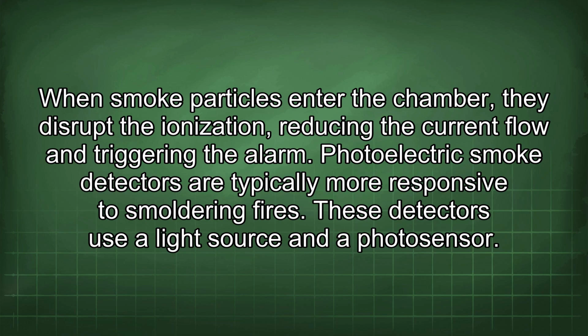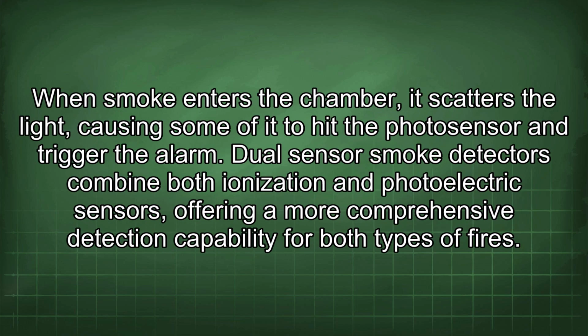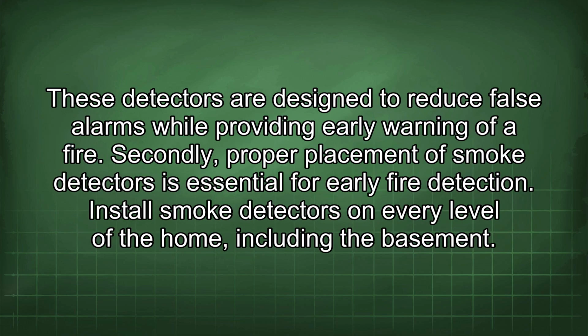Photoelectric smoke detectors are typically more responsive to smoldering fires. These detectors use a light source and a photosensor. When smoke enters the chamber, it scatters the light, causing some of it to hit the photosensor and trigger the alarm. Dual-sensor smoke detectors combine both ionization and photoelectric sensors, offering a more comprehensive detection capability for both types of fires. These detectors are designed to reduce false alarms while providing early warning of a fire.